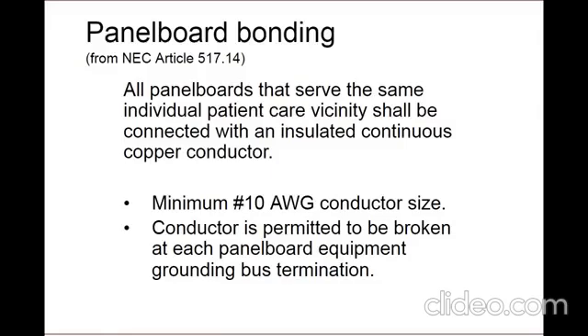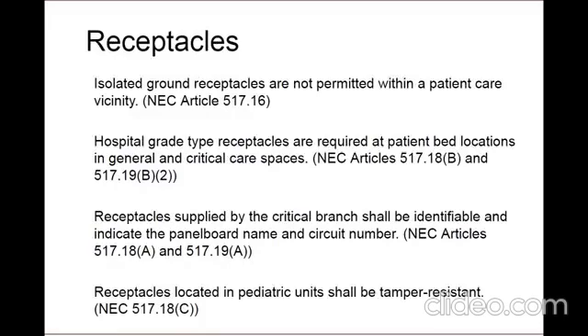There are normally 2 or more circuits that may serve a patient care vicinity. The panel boards that provide circuits to the same individual patient care vicinity must be bonded together with an insulated continuous copper conductor. The code says that the minimum conductor rating is number 10 AWG.